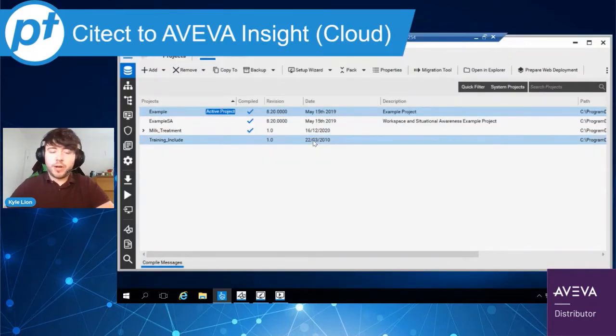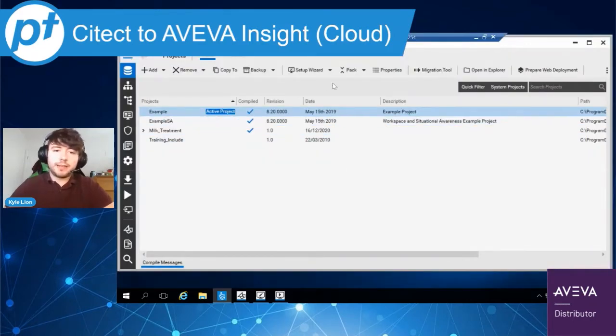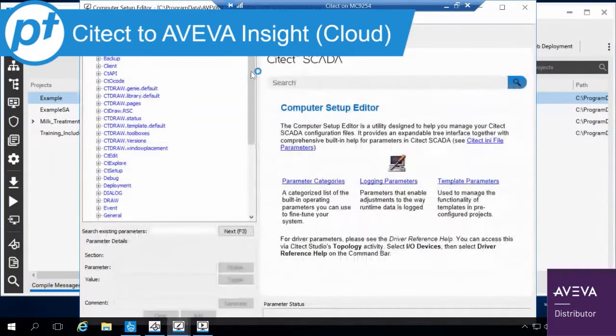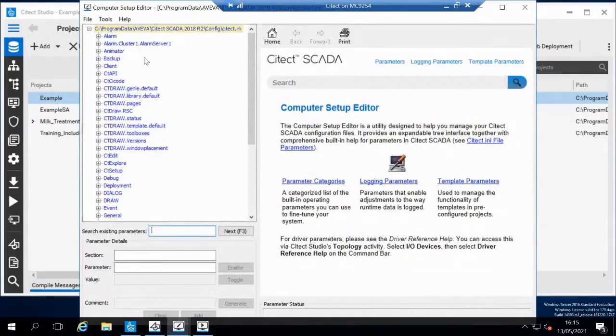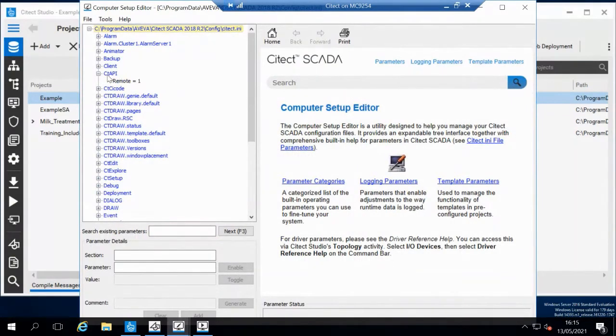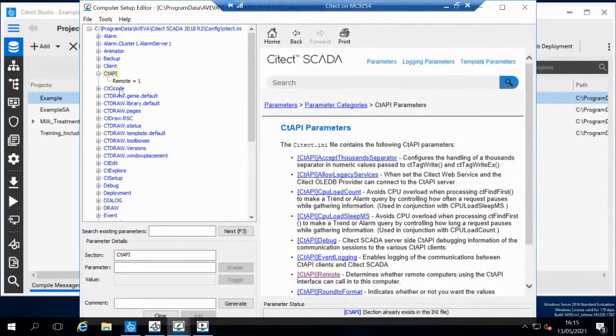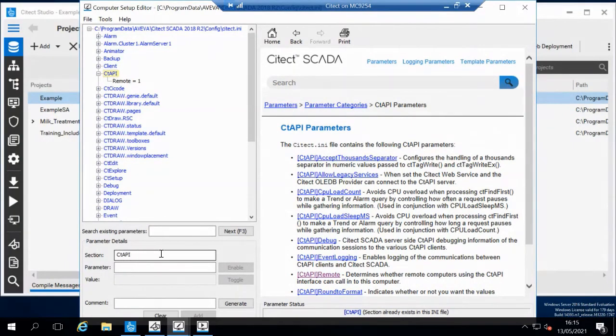To prep your Citect application, you need to enable something in the INI. If I go into Setup Editor here, you can see I've got the CT API. If this isn't in the drop-down list, you can specify it here. Just type CT API as you see it.